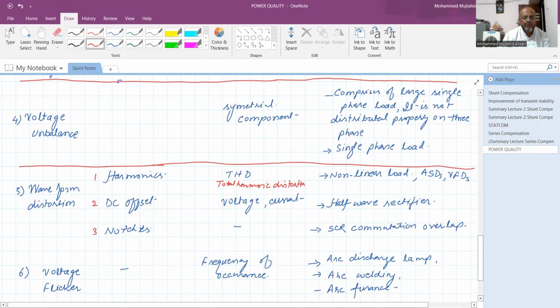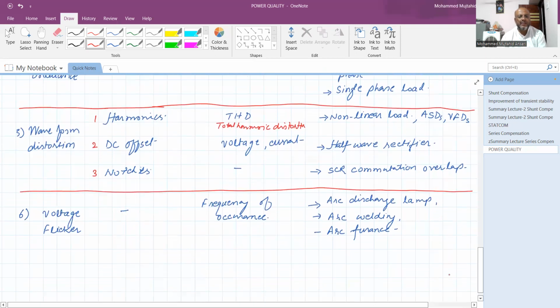The voltage flicker is characterized by frequency of occurrence, and the voltage flicker is due to arc discharge lamps like sodium vapor lamps and mercury vapor lamps. It may be arc welding and arc furnaces. So these are some categories of power quality problems, their method of characterization, and some typical causes which produce the power quality issues. So next time we'll see the categories again and some description of power quality problems. Thank you.